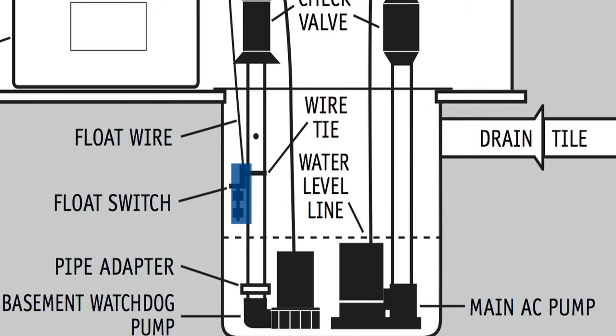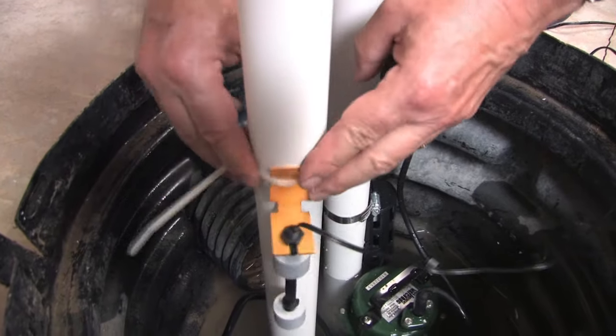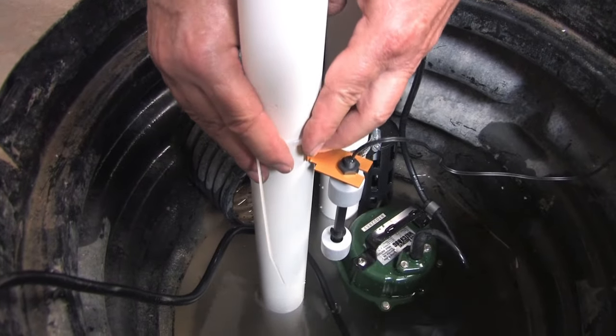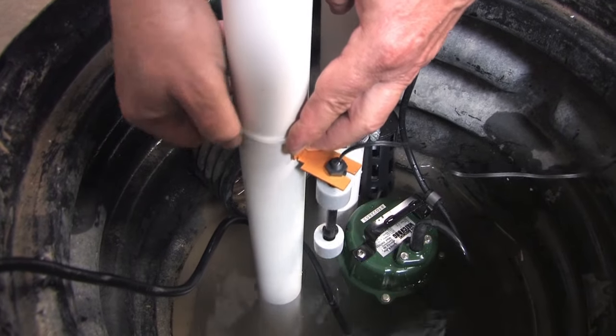The bottom of the float switch should be positioned about 6 inches above the water line in the sump pit. Attach the float switch very securely to the discharge pipe with a wire tie. Turn it away from the side of the pit where the drain tile empties into the sump so it will not be splashed by the water.